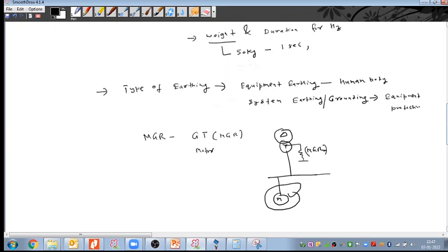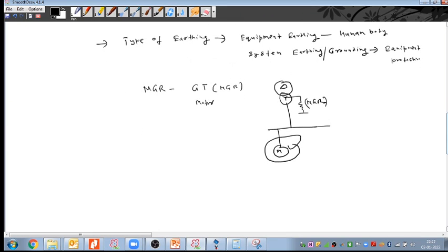Okay. One more thing: you said that the NGR rating, the maximum allowable current of the NGR, could be equal to the phase current. Here I discussed two concepts for the NGR current: how much current I want to allow. First, let me put a generator here, because a generator has its winding and its core. How much current can the core withstand? This allowable current value should be less than the withstand current of the core.